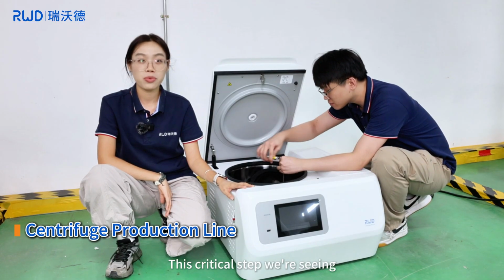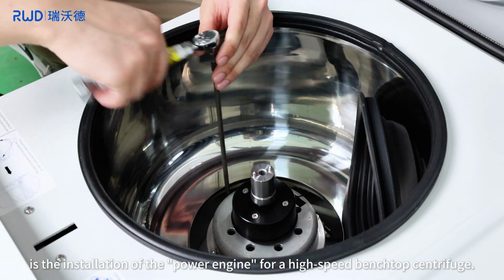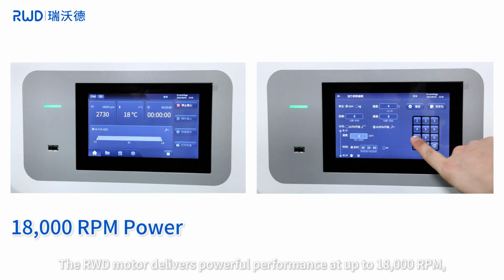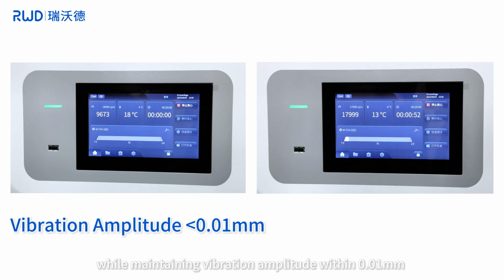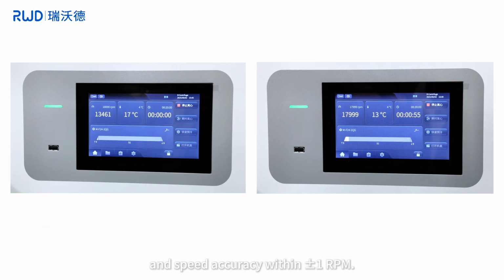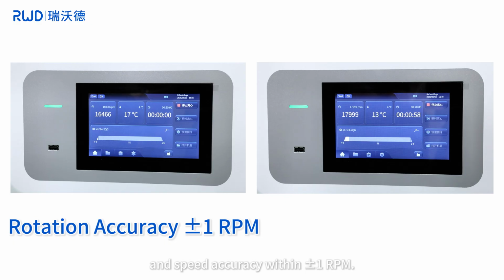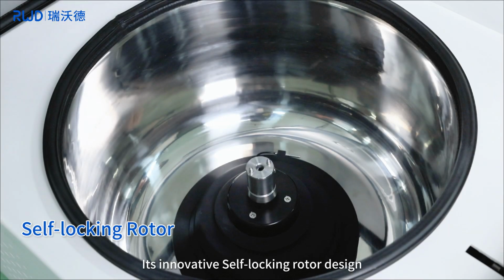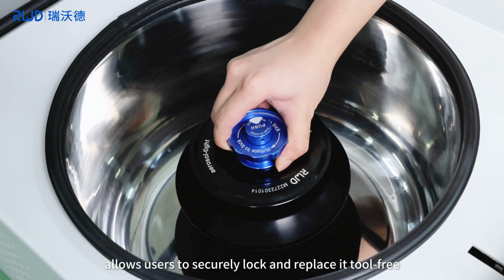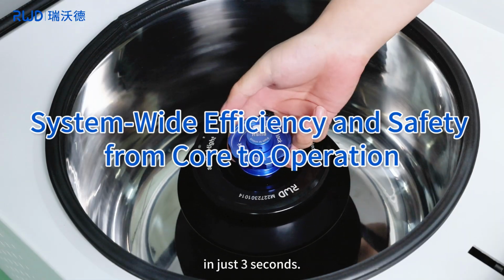This critical step we're seeing is the installation of the power engine for a high-speed benchtop centrifuge. The RWD motor delivers powerful performance at up to 18,000 revolutions per minute while maintaining vibration amplitude within 0.01 millimeters and speed accuracy within plus or minus 1 revolution per minute. Its innovative self-locking rotor design allows users to securely lock and replace it tool-free in just 3 seconds.